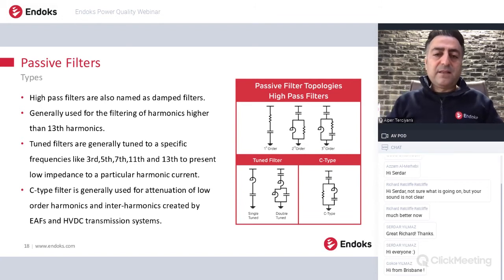And for passive filters, you can see on this slide, there are some types of passive filters. The first one, on the upper side, is the high pass filters. We mostly use these filters for eliminating the higher order frequencies, generally higher than the 13th harmonic.